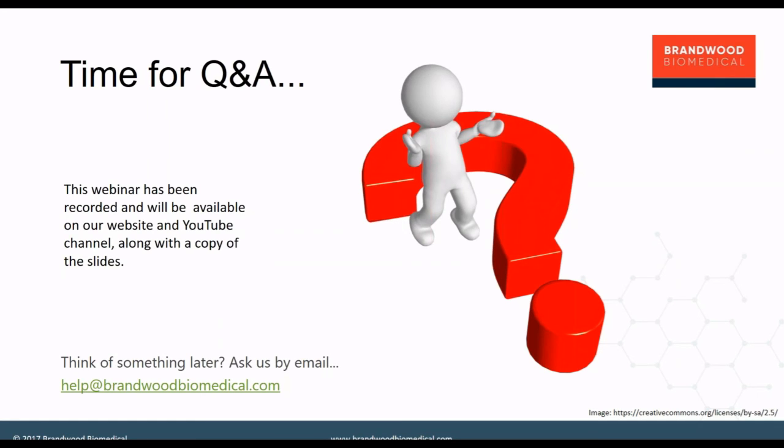Can you explain the term designed to state of the art? And what is expected by the regulator for evidence that the state of the art has been applied? Okay, so that's an excellent question. Thank you, Rob, for this. There are several aspects which are considered here. The first one is, as I mentioned before, when you put together the technical file, in order to demonstrate compliance with the regulatory requirements, you will use some harmonized standards.